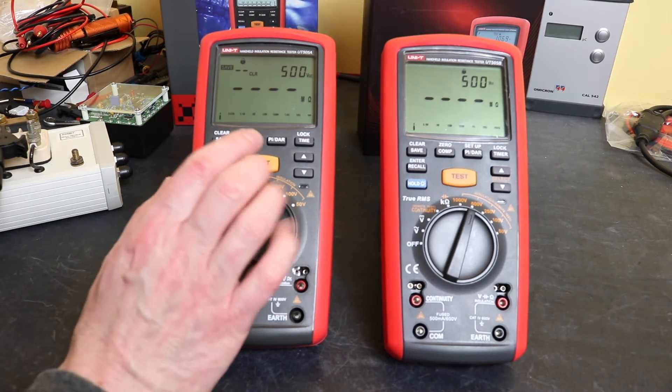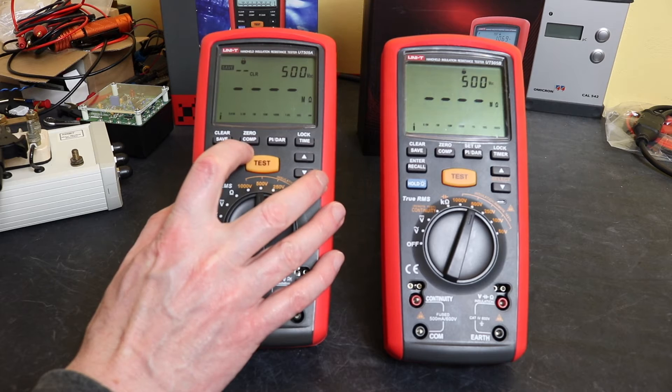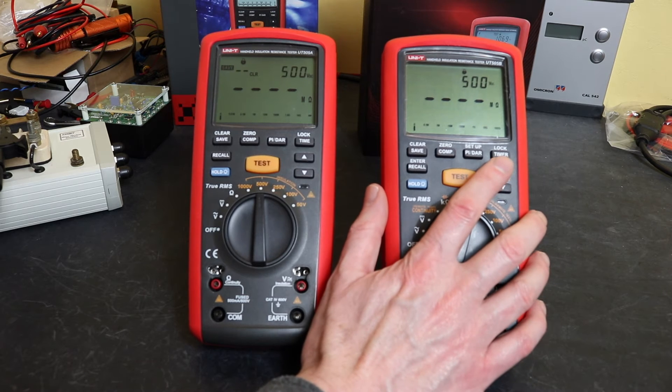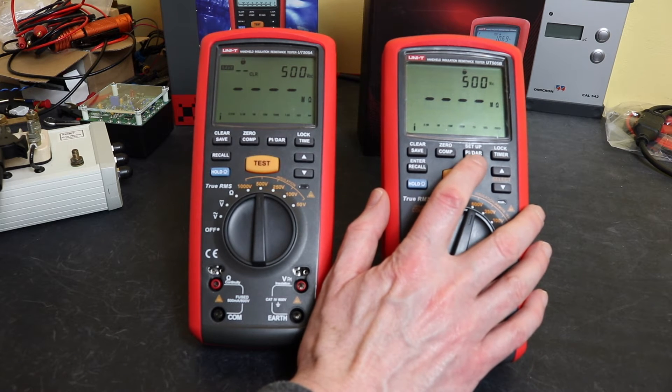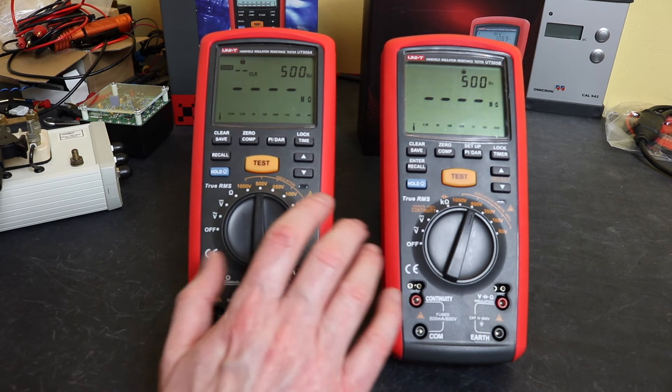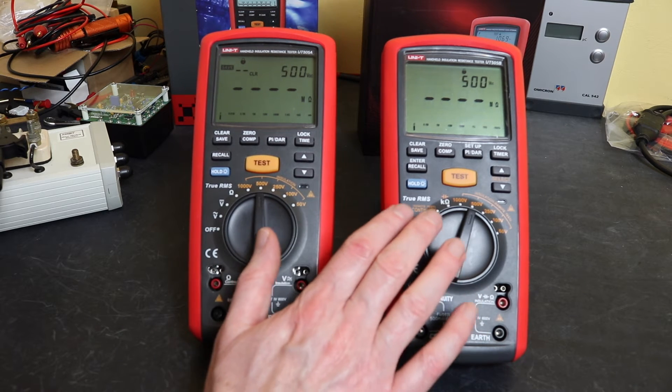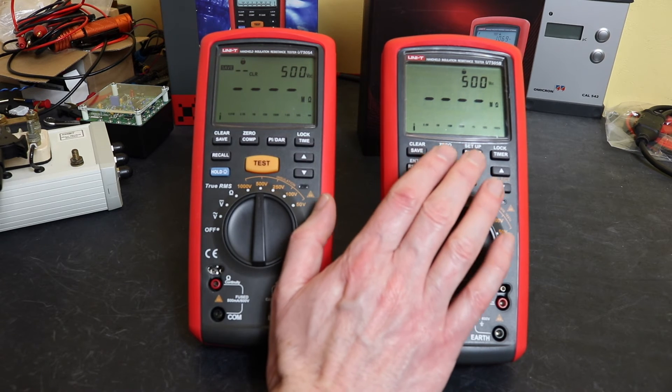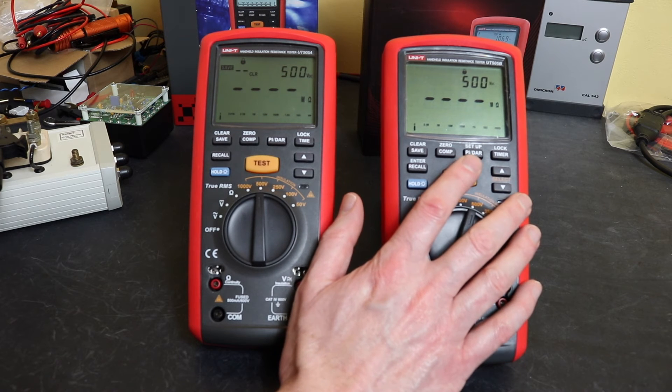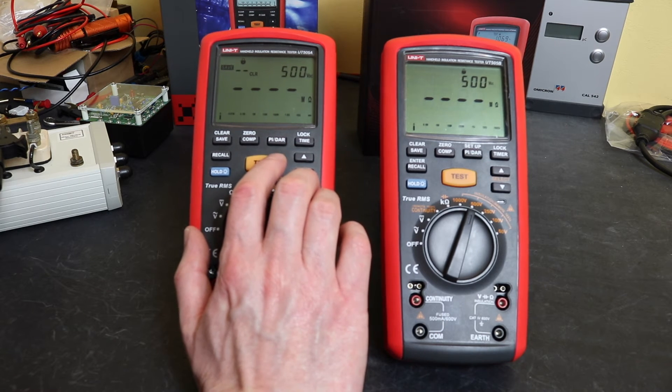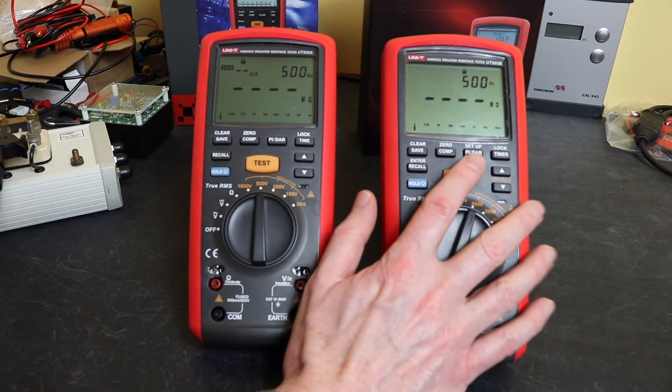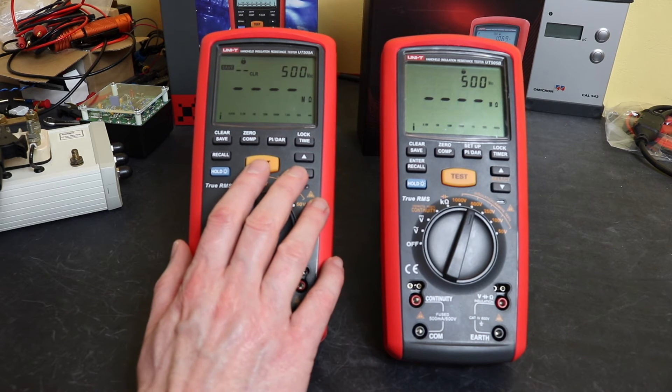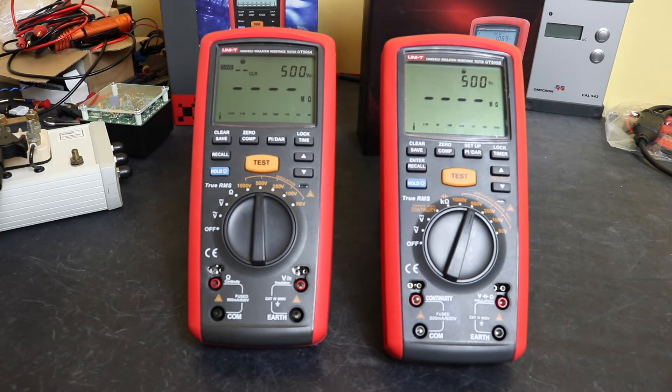With regard to the functionality on the insulation test, you do have a comparison function in there - PI and DAR and a time function. Whilst the UT505B does have the same function as that, the PI and DAR and timer do function in a slightly different manner than they do on the UT505A. You actually get the mega ohm readings whilst this is testing that you don't see with the UT505A, and they do cut off at the end of the PI and DAR test as well, whereas the UT505A you do have to stop manually. However, at the end of the test you do lose the mega ohm resistance - that's just replaced with the actual ratio for the PI and DAR, whereas you can see the mega ohm reading and the PI and DAR ratio on the UT505A.